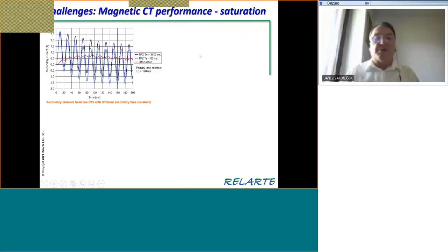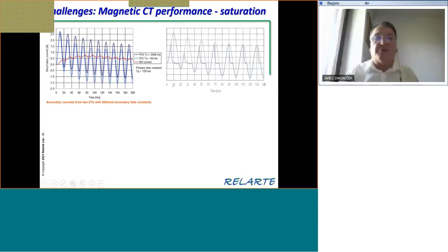When discussing merging units or standalone merging units, they will still get signals from such magnetic transformers. There's a bit about TPX and TPZ transformers, which have different secondary time constants: TPX are transformers without air gap, TPZ are those having a big air gap. You can see how they perform differently at high fault current with different time constants. So if you have two such different transformers, you simply cannot use them for differential protection. But that's just for information.